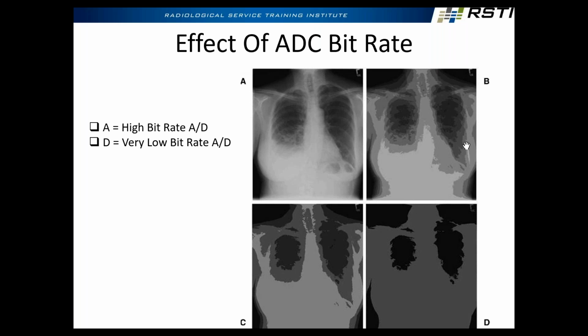We have the ability to see small things, but I need to be able to see differences in those three tissues in the breast. That's what really differentiates seeing adipose tissue and cancerous tissue. Very, very important that we can see those contrasts, especially in mammo. So I just gave some examples here of different bit depths, right? This could be like a 4-bit. With increased bit depth, you can see it's the same image, but when you have a lower bit depth, it's taking all the similar shades of gray and making them into one, right? And you're losing that information. So lower A to D converter, higher A to D converter, more shades of gray.